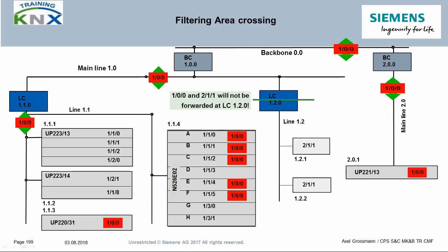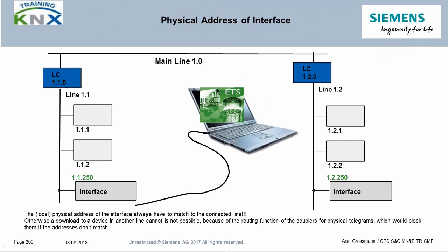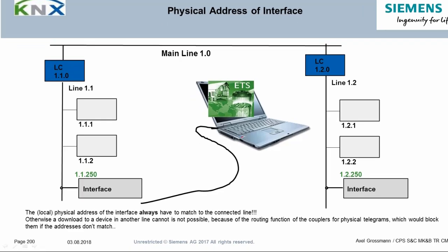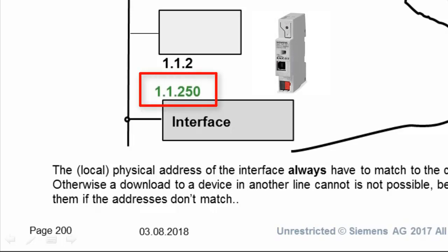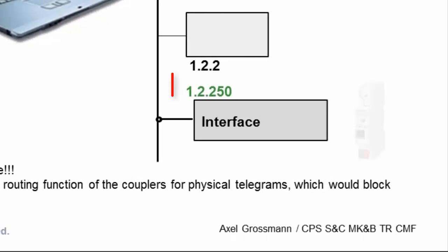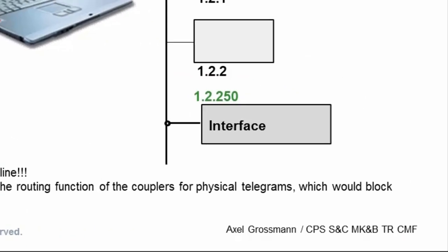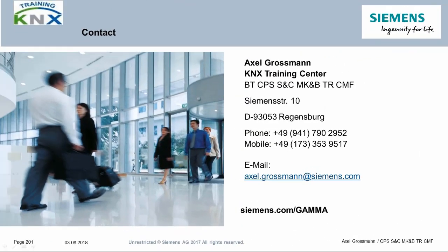This is the same example as with the brightness sensor seen before. Last hint and reminder: when doing commissioning or maintenance work, always make sure to use a line-compliant local address of the interface between the ETS computer and the KNX bus. In our example, if you connect your PC to an interface in line 1.1, the individual address of this interface must also begin with 1.1; if you do so in line 1.2, the interface must be addressed like 1.2.xxx. This is the end of the KNX system theory. Congratulations and thank you very much for your participation in this training. If you are interested in becoming a certified KNX professional — participating in a two-day exam course — don't hesitate to contact me.